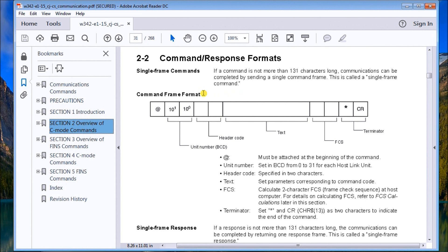In our case the text will be the starting address and the number of data memories we're going to read. Then we have what we call a checksum calculation — the FCS. It performs a mathematical calculation and gives you a two-character result so the controller can read the FCS and make sure nothing changed during transmission. Finally, the command ends with an asterisk and a carriage return that indicate the termination — the end of the message.